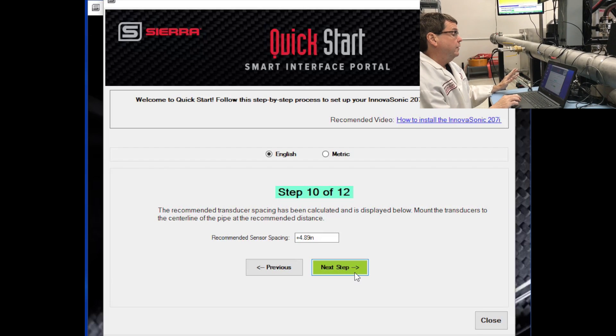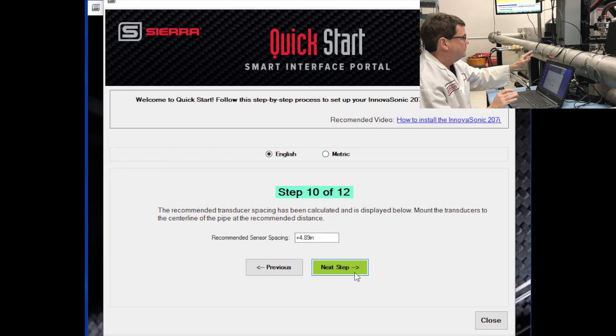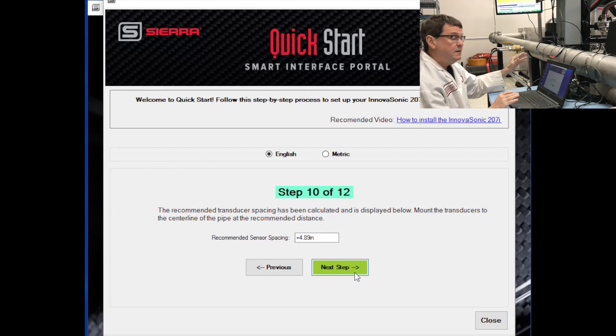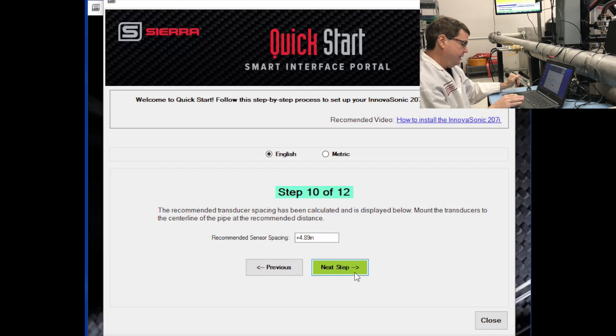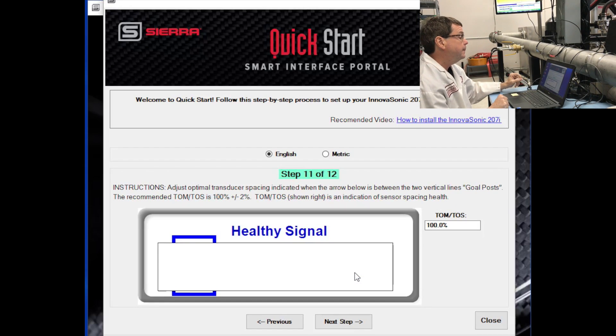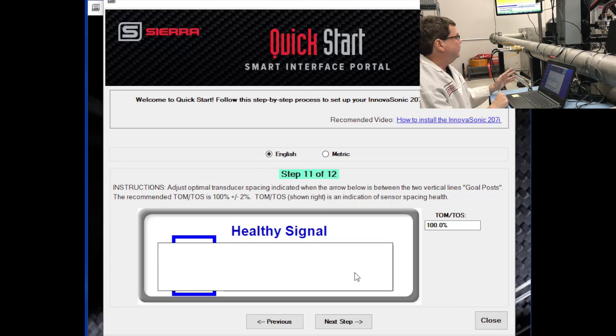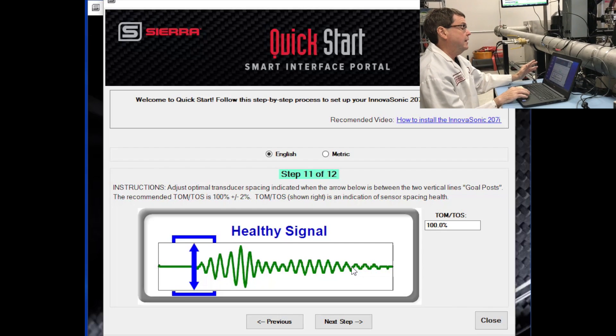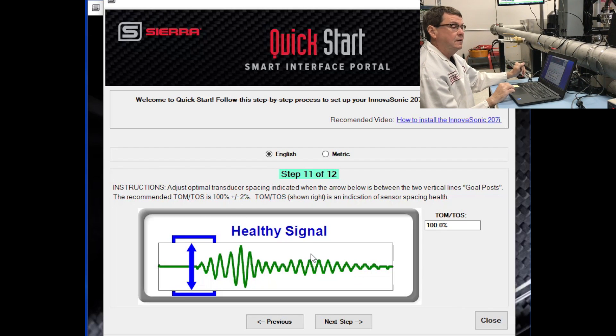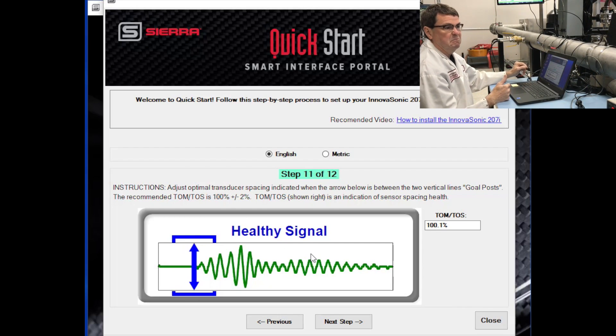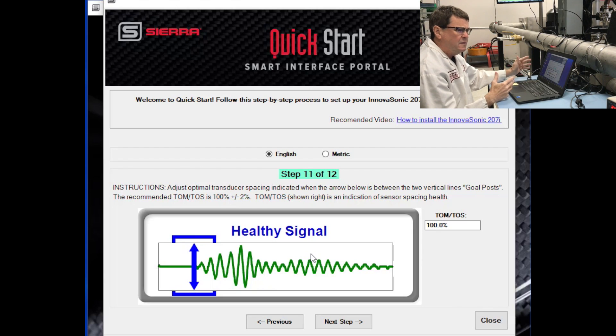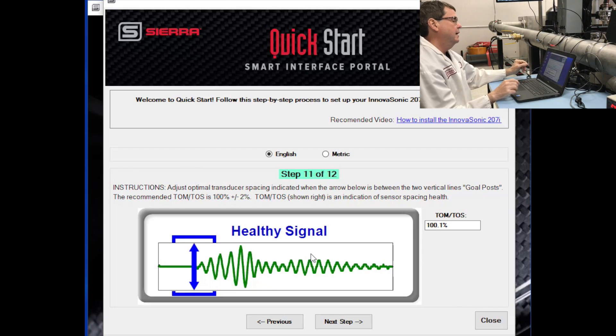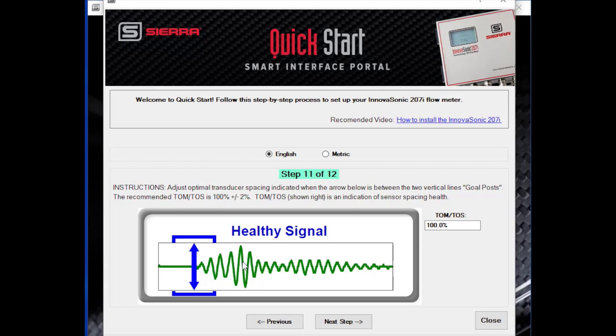Alright. So we're finishing up. We've put our transducers on the pipe. We've approximated the spacing. Now it's time to fine-tune our transducer spacing. In step 11, the meter is going to evaluate transducer spacing and it is going to actually show us what the signal looks like and make some determinations about is this a healthy signal or is this a good signal or is this a poor signal. So let's take a look at what we are seeing here.